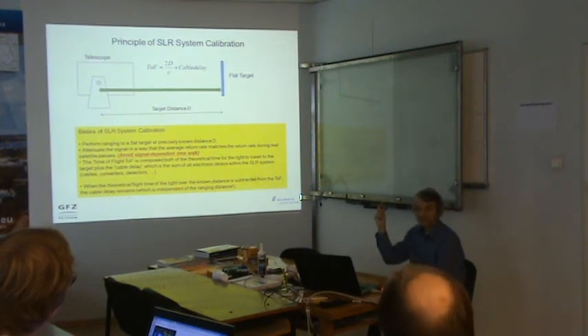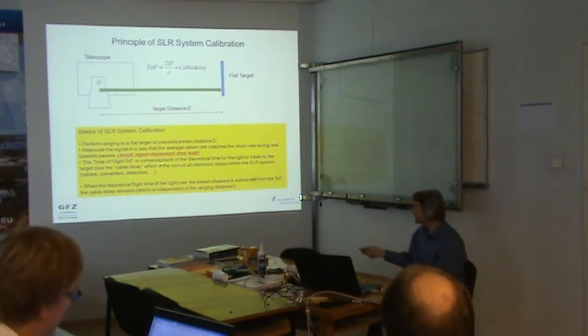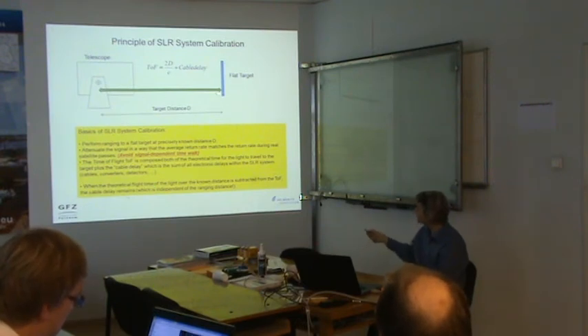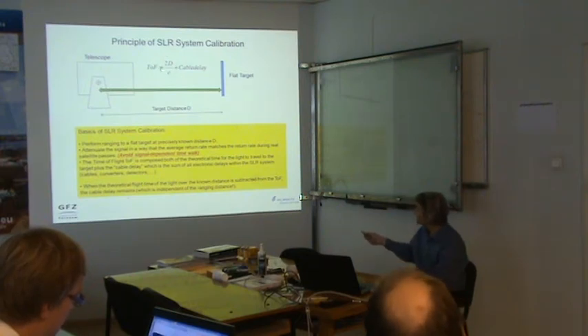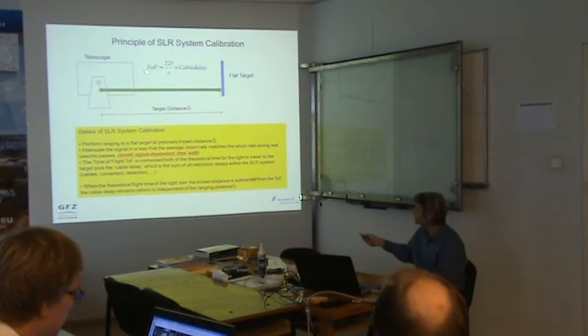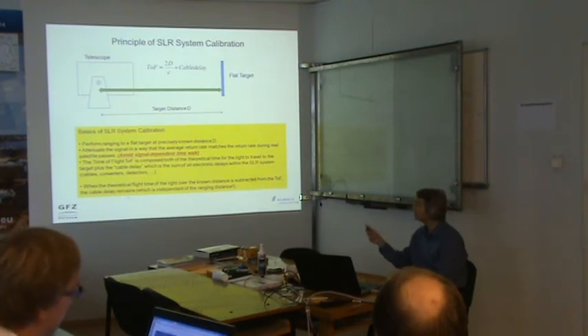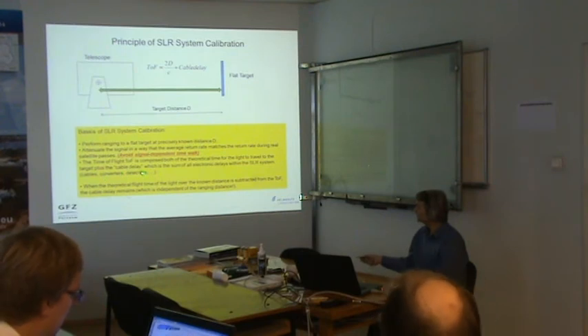I have some numerical examples for you later. When we know the theoretical time of flight over a short or a little bit longer distance d, then we can subtract the theoretical time of flight from the measured time of flight to find out the error. Here we have the cable delay, which is the sum of all the elements: the cables, the converters, and the detectors.